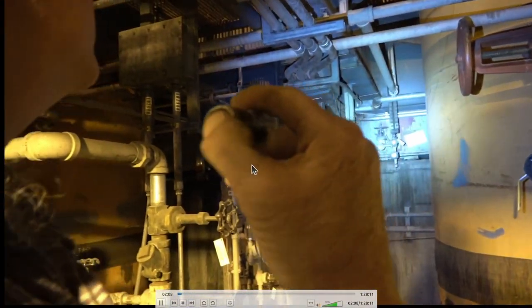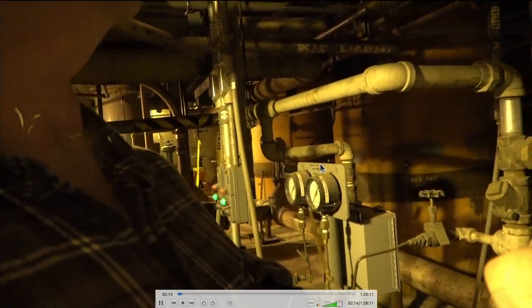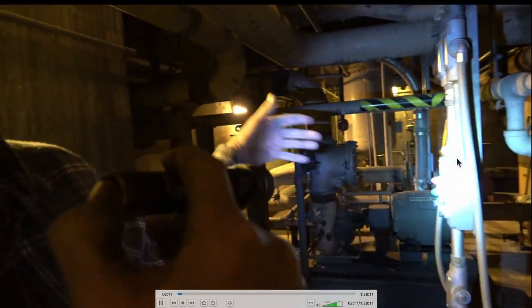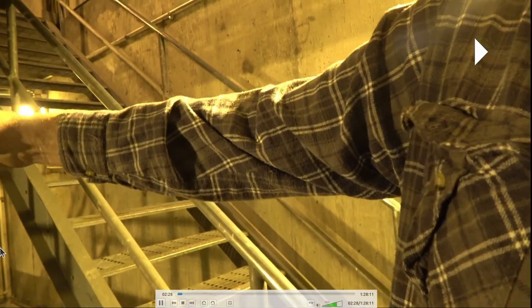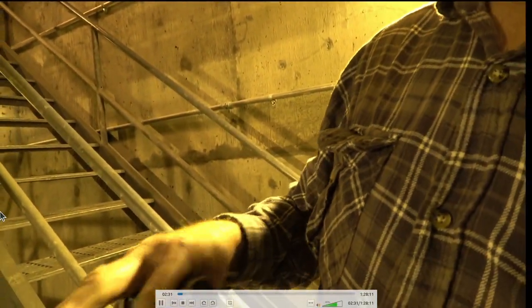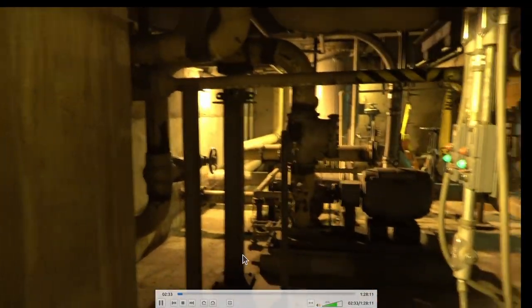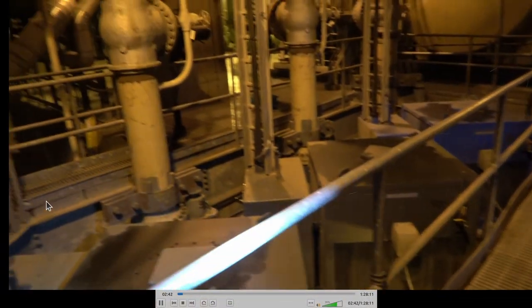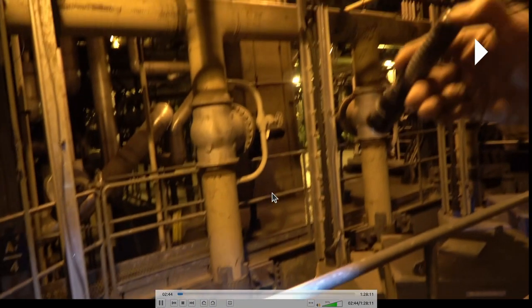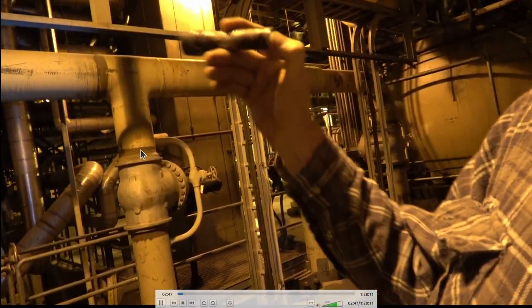You can see where a potential leak is in the tubes. There's a pump back here for pumping out the hot well. This is the condensate pit down underneath the first floor; there's a transfer pump that moves condensate out. Here's your main condensate line coming in. These are the minimum flow recirc valves — these pumps have to have minimum flow on them, so there's a little recirc valve that maintains minimum flow.